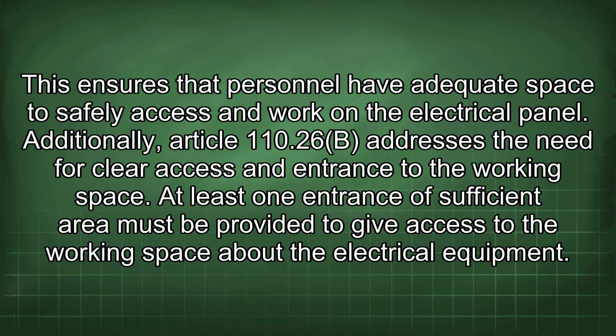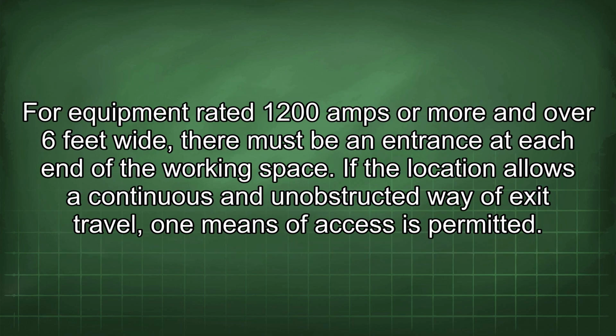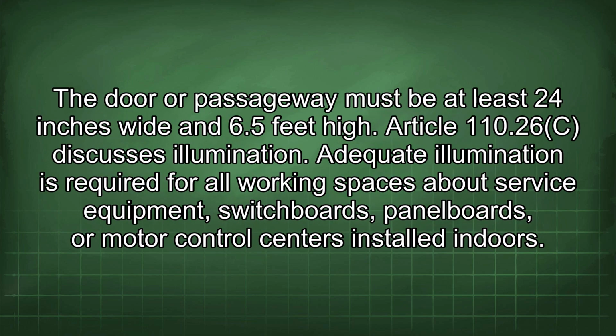Additionally, Article 110.26(B) addresses the need for clear access and entrance to the working space. At least one entrance of sufficient area must be provided to give access to the working space about the electrical equipment. For equipment rated 1200 amps or more and over 6 feet wide, there must be an entrance at each end of the working space. If the location allows a continuous and unobstructed way of exit travel, one means of access is permitted. The door or passageway must be at least 24 inches wide and 6.5 feet high.